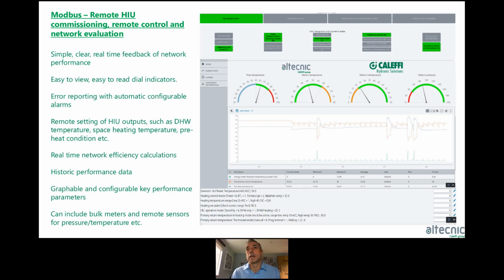And then here in the graph in the center is historic data that goes back as long as the system's been running. And you can go back, you can see what's happening to the delta T. You can graph many things on here. Anything that's being read by the Modbus, which is up to 250 bits of data. You can just pull them out and put them into the graph. So whichever parameters you want to view, whatever you think is important to you, you can show on this graph and see what's happened. And then you can simply zoom in, and it's averaged out or shown in the table here what the maximum, minimum and average values are, and so on.